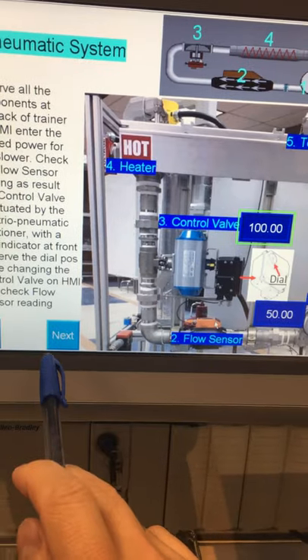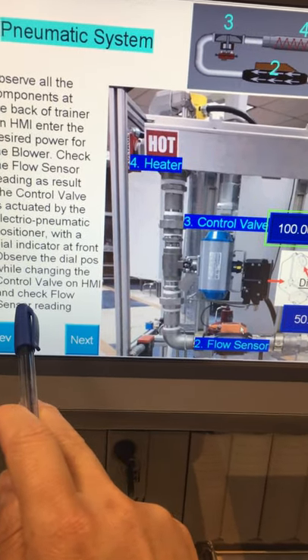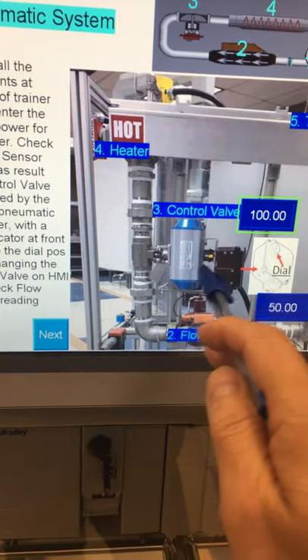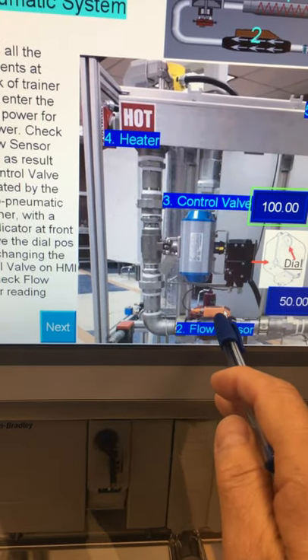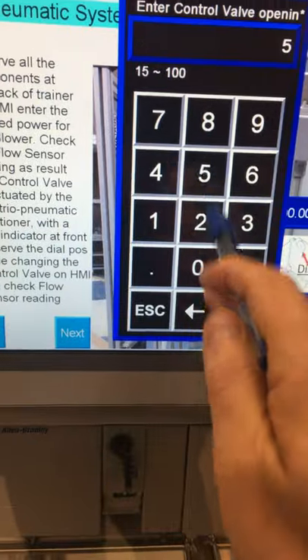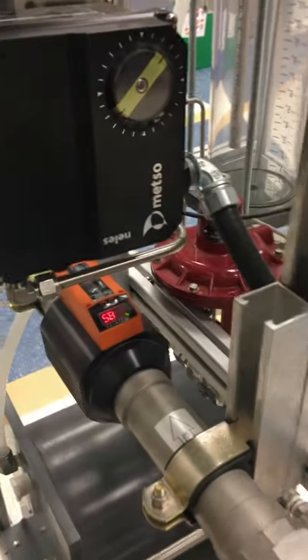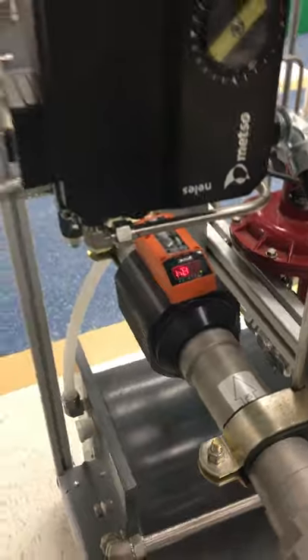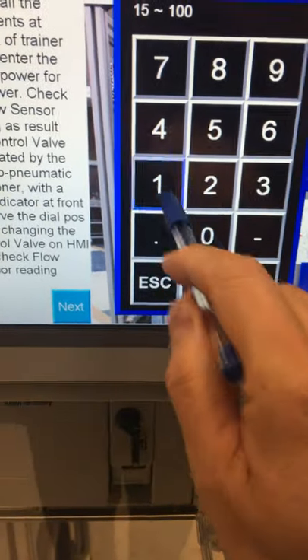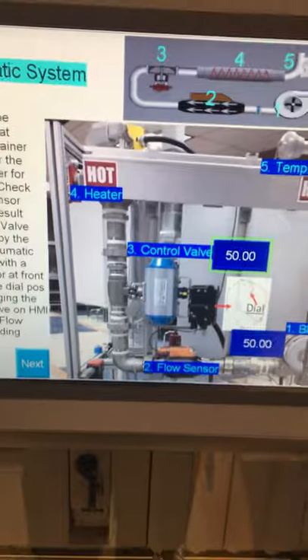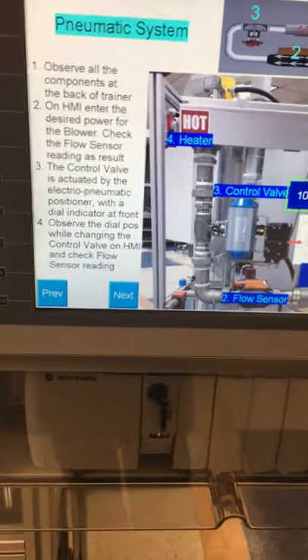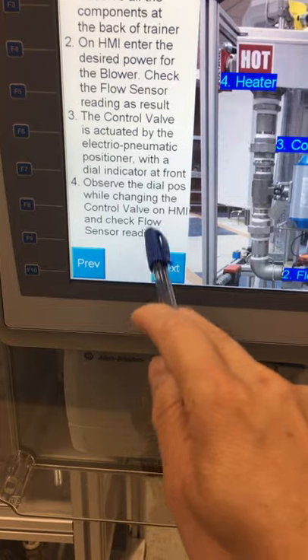So let's look at the next, all right? Before, I should have let you look at the control valve, which should also control the flow, right? Let's look at it. 50%. If we look at that, before it was 42 something, right? So right now you're reading 8.2, because it's shut down to 50% opening. So that's why this has the effect on the flow sensor. Okay, so this is the part, the observation.